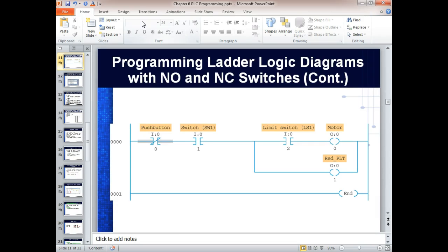Are you okay on what we call a scan? What's a scan? So what does the PLC do when it starts running? Okay. Yeah, it starts scanning the ladder. Starts over here and scans across, scans across. So it starts in the upper left-hand corner. Input first, output last, and then it ends up down at the very bottom of your ladder diagram in the lower right hand corner.